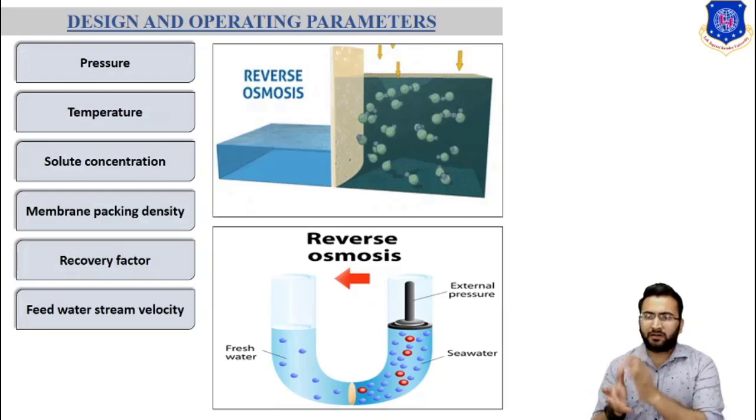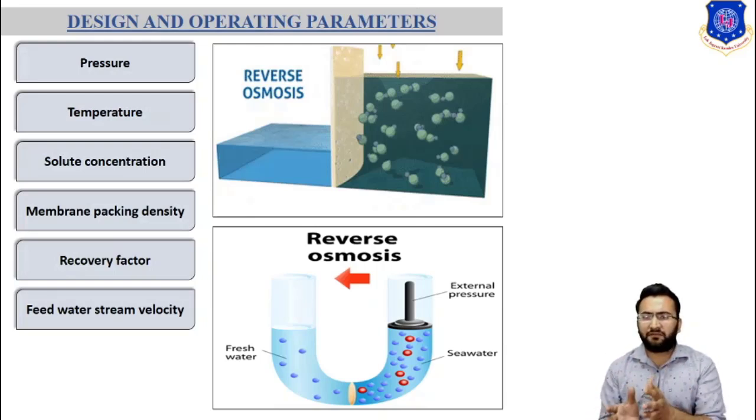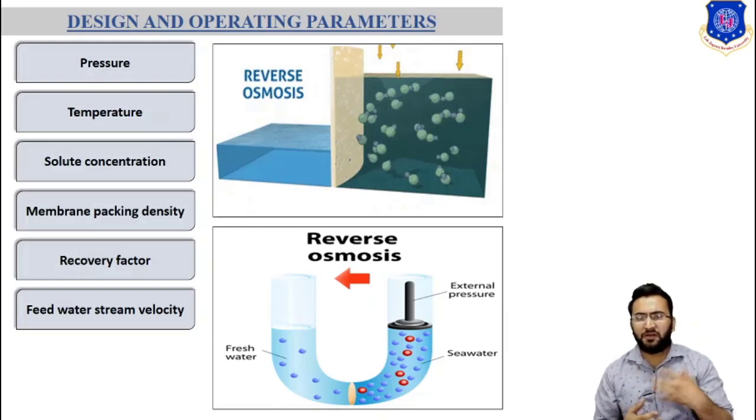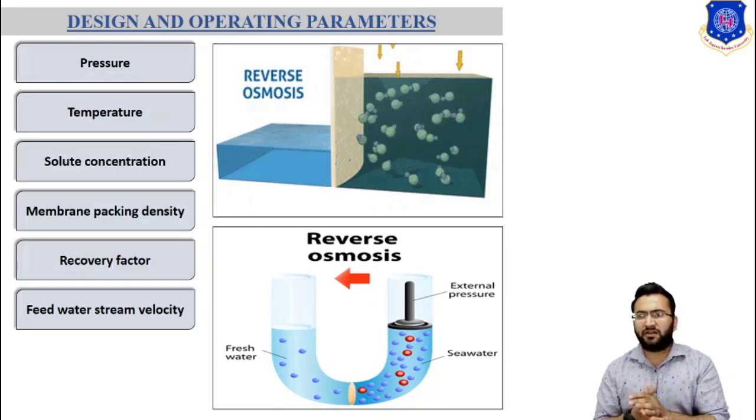The recovery factor actually represents plant capacity and is generally in the range of 75 to 95%, with 80% being the practical maximum. At a high recovery factor there is a greater salt concentration in processed water as well as in brine. At a higher concentration, salt precipitation on the membrane increases, causing a reduction in separation efficiency.